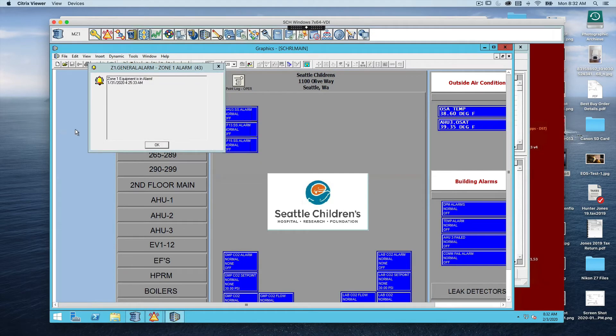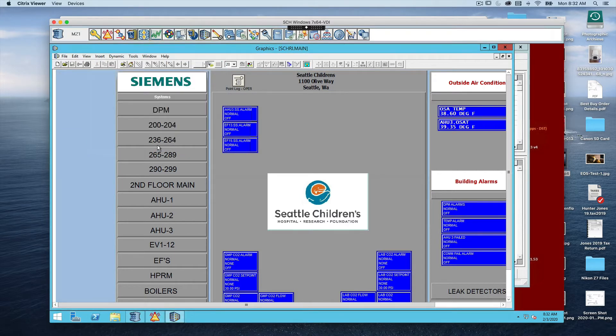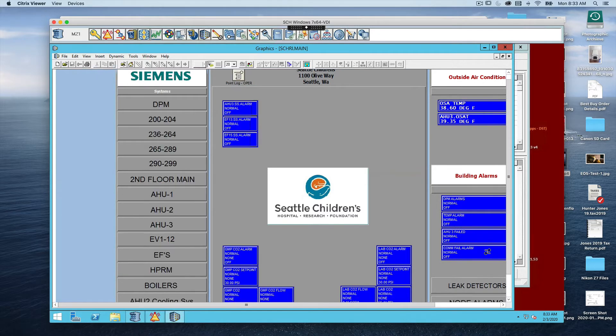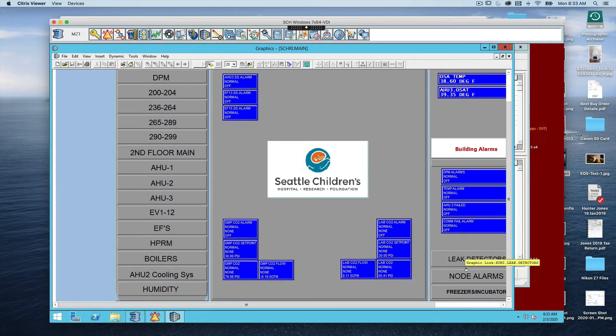We double-click to enter the Insight program, which is the Apogee building automation program for Siemens. Insight loads up and brings us to what they call the main screen. When you load up it'll bring up any alarm notifications currently in process — we can hit OK to acknowledge those and go back to our main screen. This main screen has a number of items: on the left are all your building systems, in the center are major alarm systems, and on the right are outside air conditions and building alarm systems. Scrolling down we can also see leak detectors, node alarms, freezers, and incubators.